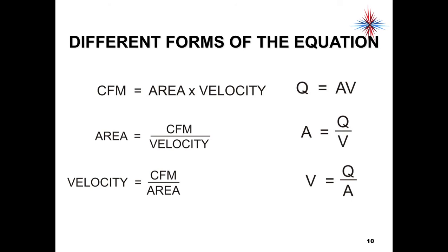So just to recap, CFM is the amount of air being delivered through the ductwork. Velocity is how fast the air is being delivered. I have to have 400 CFM of air coming across the cooling coil at a certain speed per ton of air conditioning to make everything work correctly. And we'll continue on from there in the next lesson.